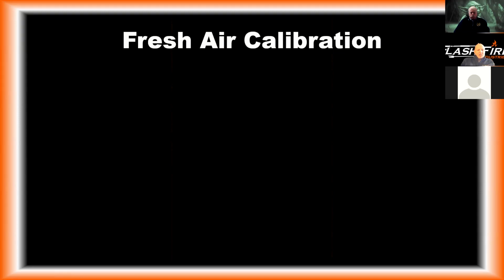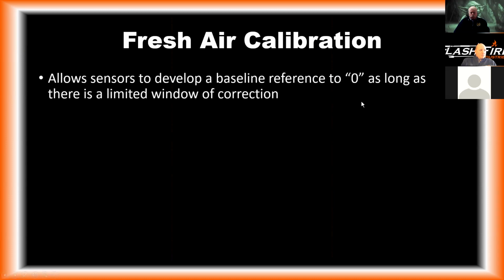Fresh air calibration. This is probably the most important thing that you can do on a general maintenance level to make sure that your meters are working properly. I haven't found a better example, so I just say that this is kind of the equivalent of having your PASS alarm go off and taking the pack out of service without trying to reset it first. Okay, fresh air calibration is the first thing you should do if you have any issues with your meter.